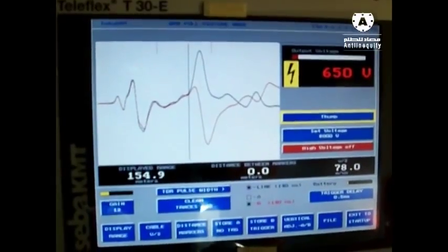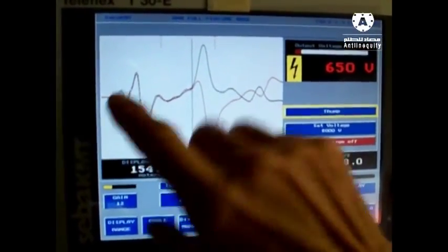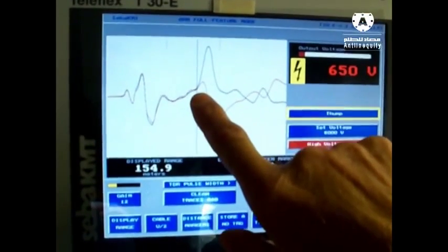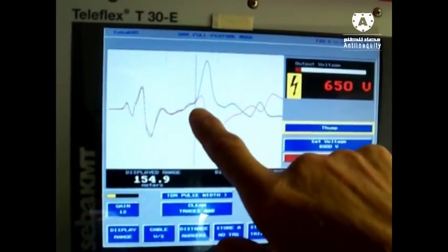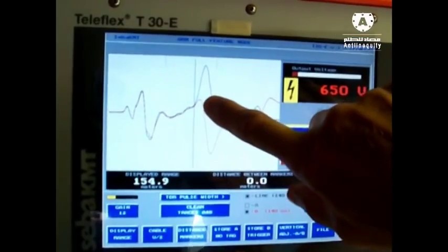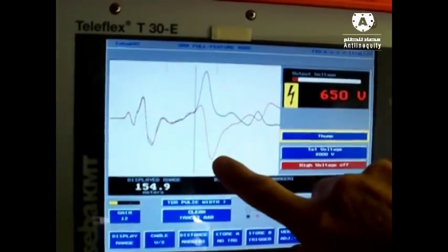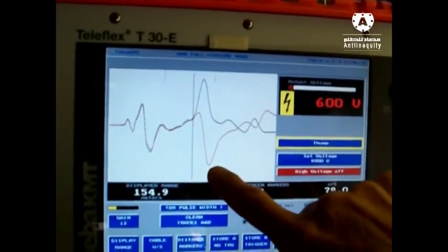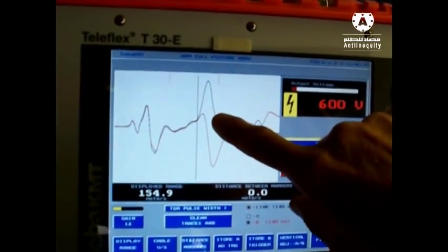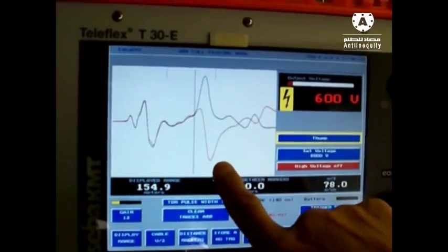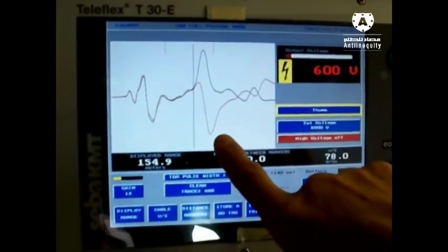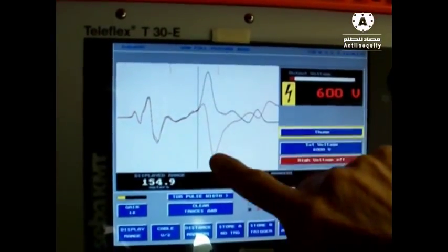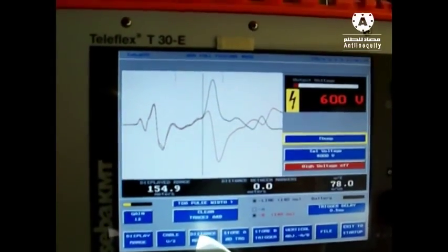And what we see here is the beginning of our TDR. The impulse is moving, nothing is different to the healthy picture, but at the end we get a flash over. We create a 0 ohm resistance fault by a flash over by the high voltage, and 0 ohm resistance means in TDR measurements that the curve goes down to 0, to minus. And we're divided into two curves. This is our point where our cable fault is.